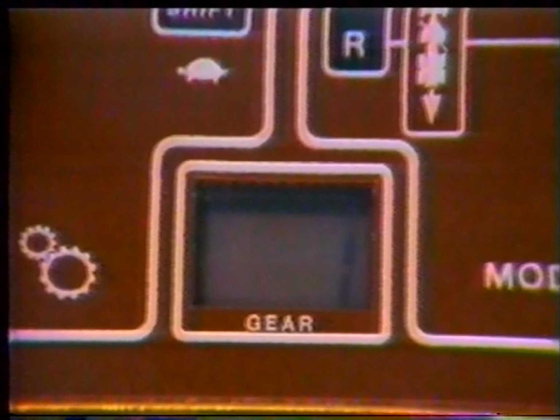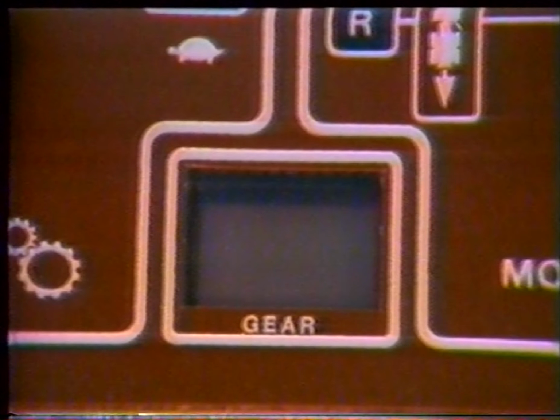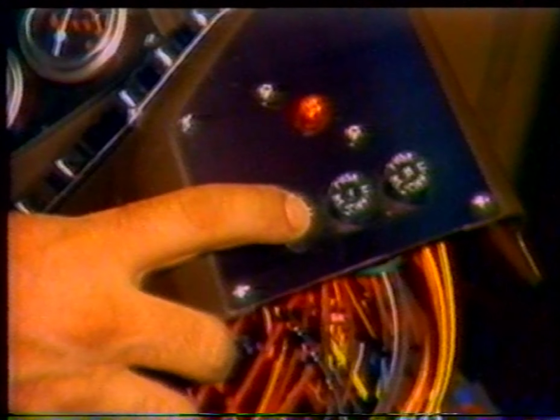E2.7 indicates an open circuit in the power supply to all 6 solenoids. The first check is at the 15 amp circuit breaker. If the breaker is OK, check for power at the continuous duty solenoid.